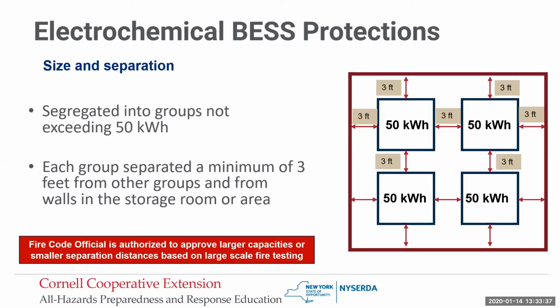One of them is the size and separation requirement. You want to have 3 feet between any of the blocks of batteries. You don't want any block to be greater than 50 kilowatt hours, and this is to reduce the spread of fire should it occur, which again should be rare if the rest of the fire code is followed. In the lower left-hand corner of the screen in red, text says the fire code official is authorized to approve larger capacities or smaller separation distances based on large-scale fire testing.